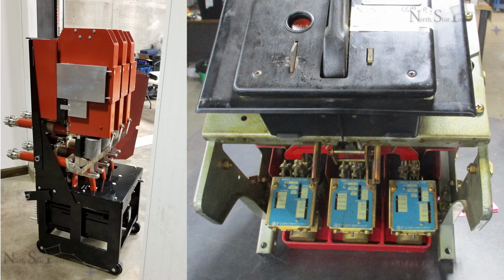If a trip unit has been in service and the settings have never been changed despite updates to machinery and other protected components, the facility may be out of date on its power surveys, and the breaker may not be protecting the equipment the way it is meant to.